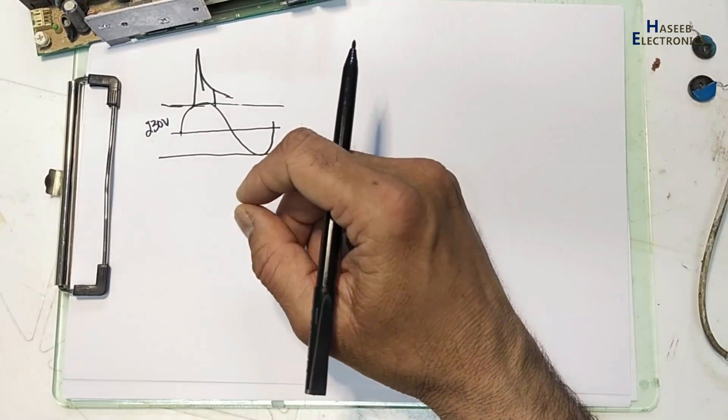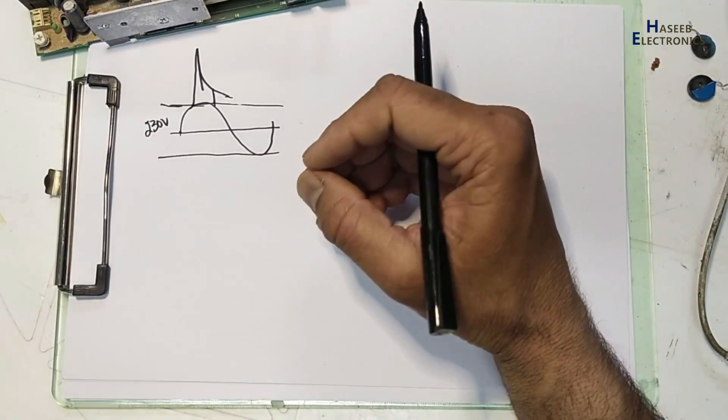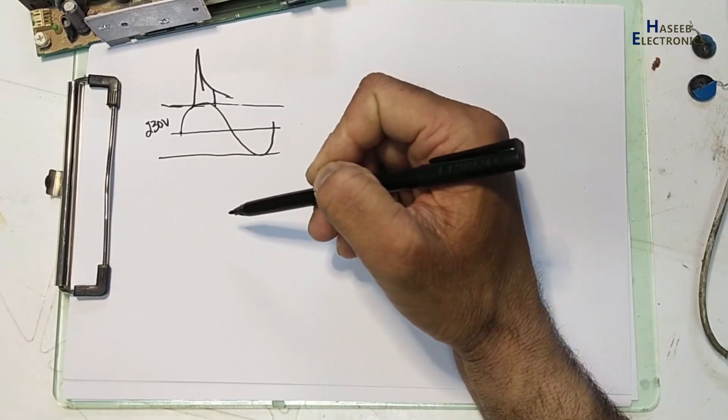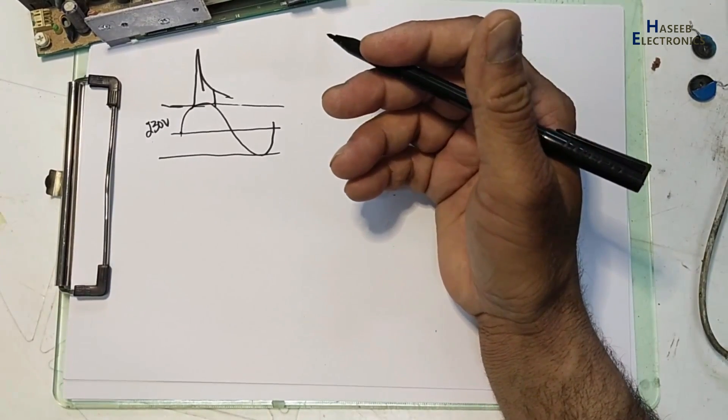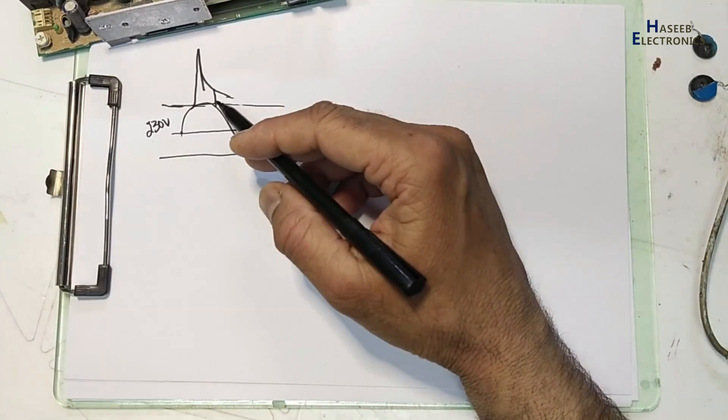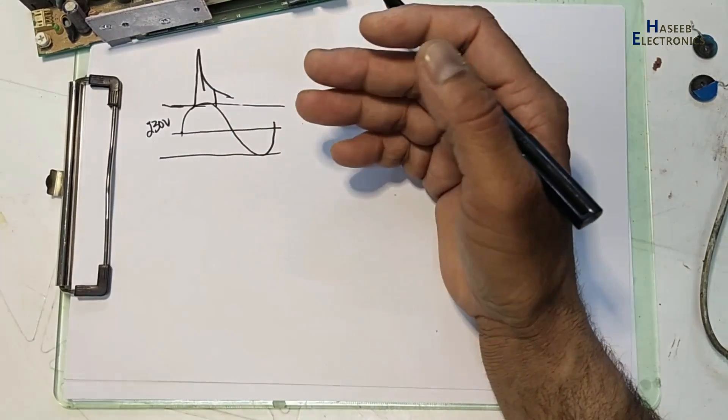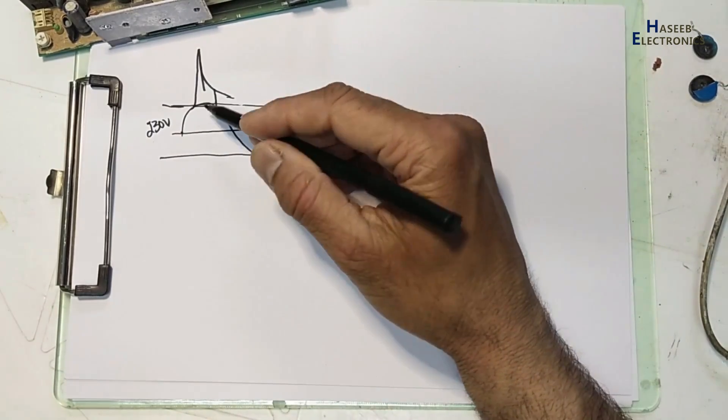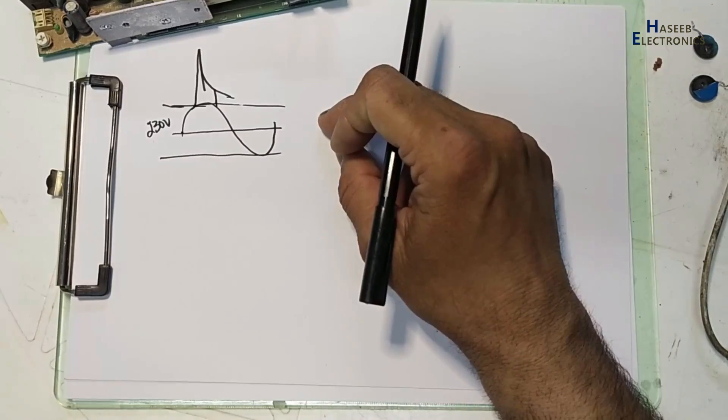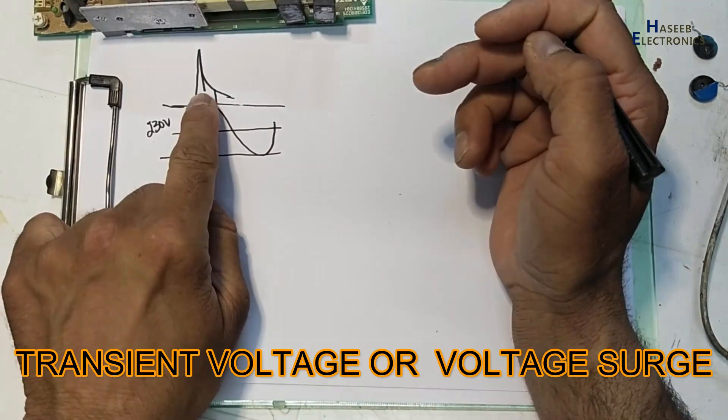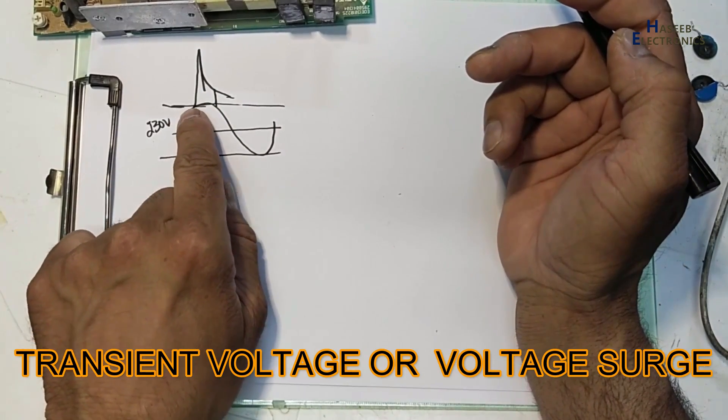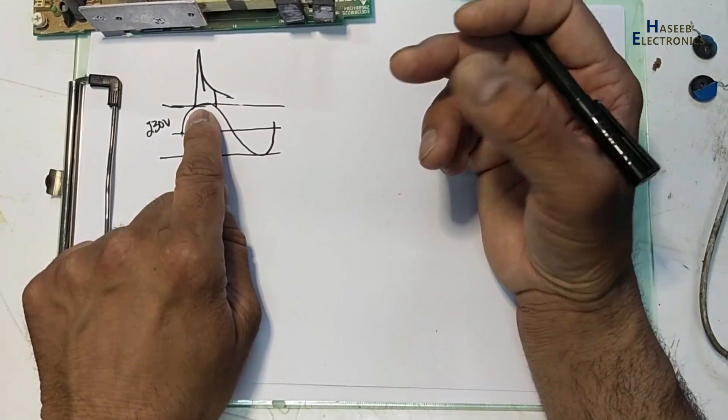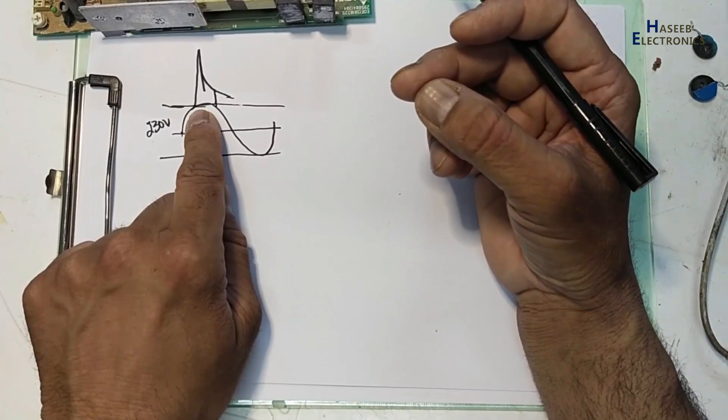If there is any electromagnetic pulse, any type of explosion, the line voltage will disturb. If there is electrostatic discharge, that can reach up to 15 kilovolts. From lightning strike, the current will be approximately 20,000 amperes. For switching, that pulse can produce 500 ampere current in just 50 microseconds.